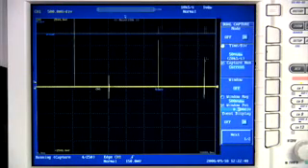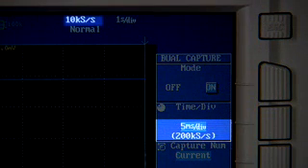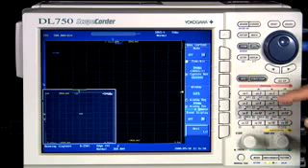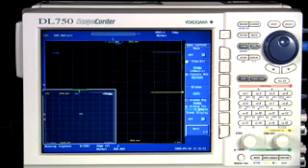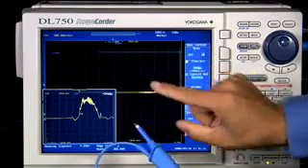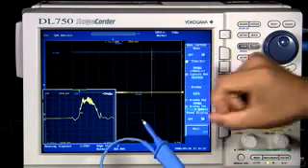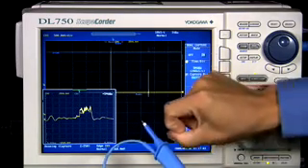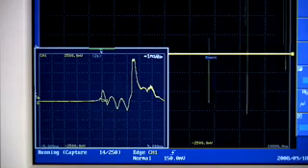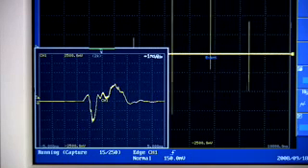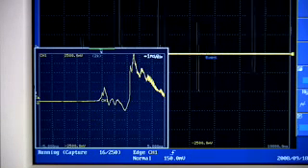Another unique function available in the ScopeCorder is its Dual Capture feature, which lets you configure both high-speed and low-speed rates. In this mode, the DL750 continuously logs data at the low-speed rate until a trigger condition is met. At the higher sample rate, the ScopeCorder acquires a transient waveform with multiple waveforms for multiple triggers, all while continuously logging at the low-speed rate.